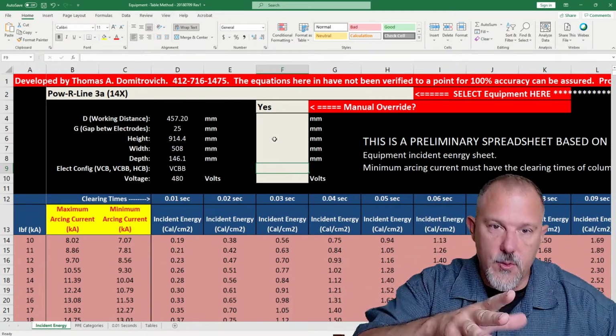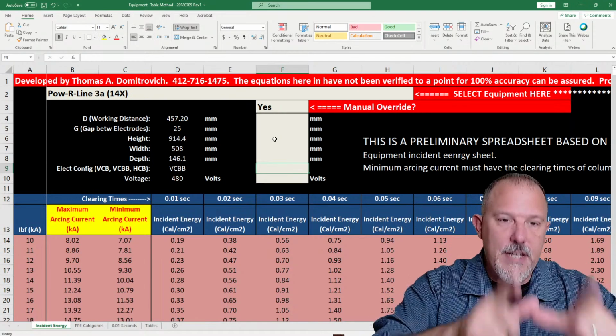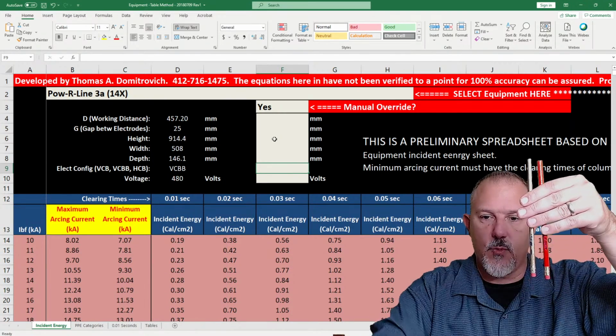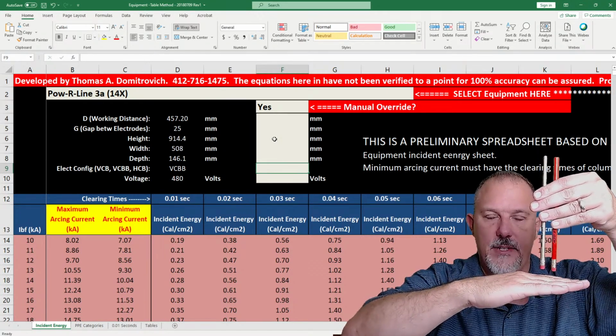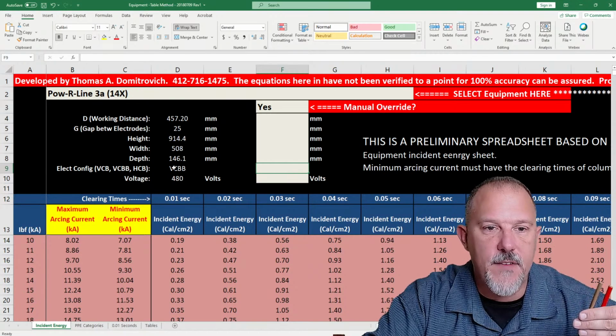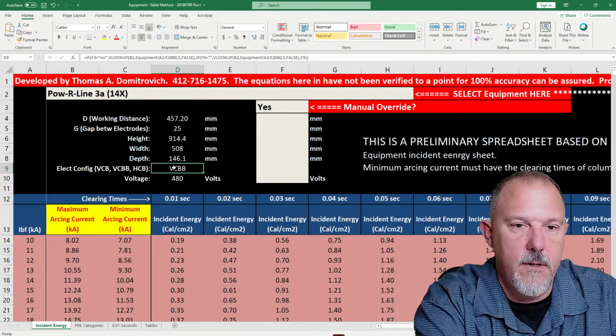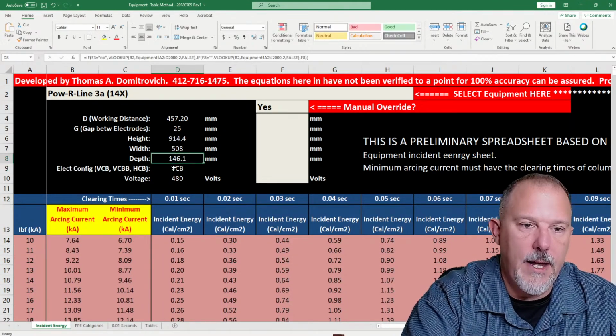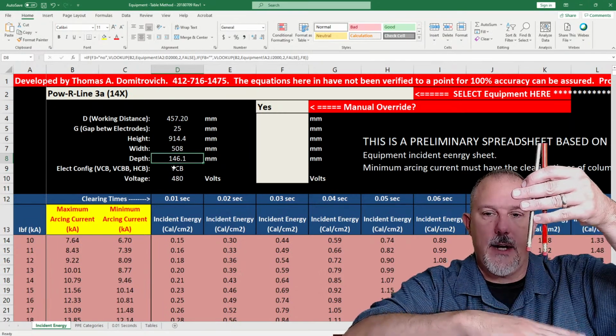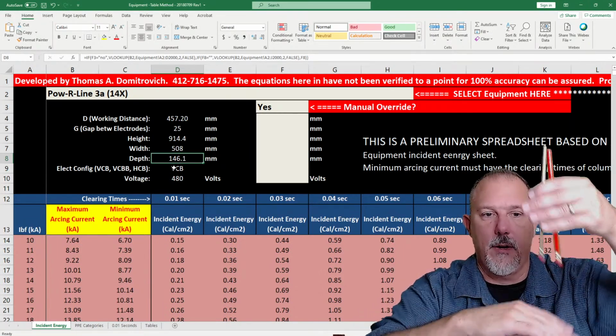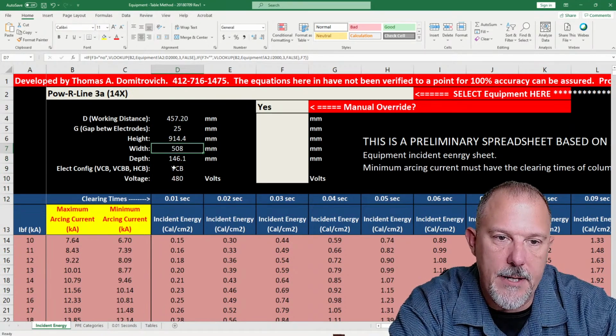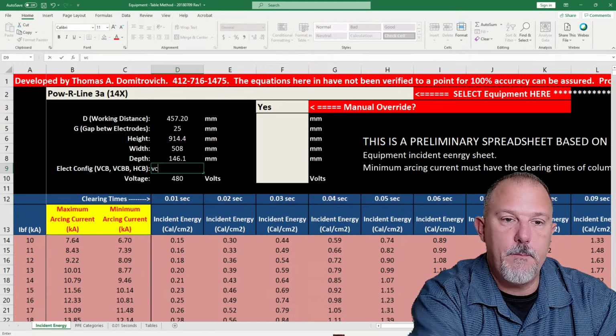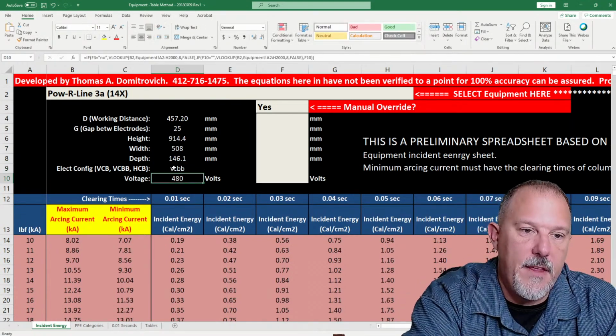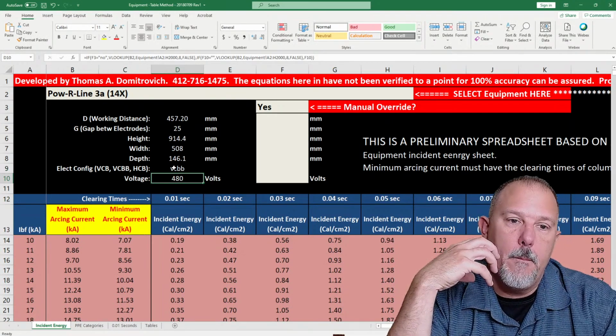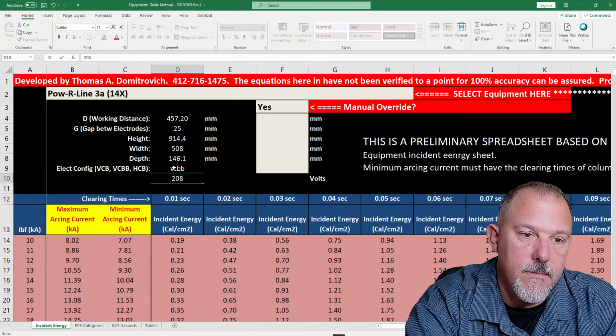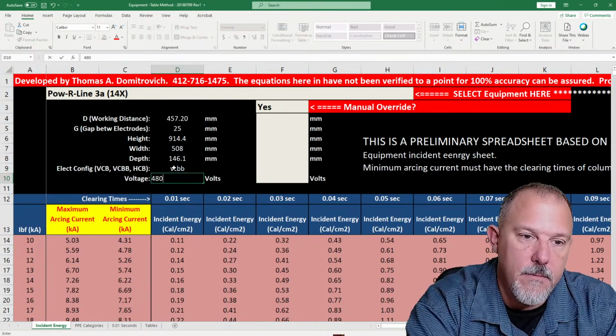Okay, so here's what happens. So I got the arc flowing away from the source. So VCBB means if I have my bus this way, if I have an insulated barrier at the end of this bus, then I use VCBB. If I use VCB, as opposed to VCBB, VCB means I have space below this. It's not an insulated barrier. But look what happened when I changed it from VCB to VCBB. Watch the arcing currents. They change. So now in voltage, obviously, if I take this to 208, my arcing currents are going to change. 480, my arcing currents change.